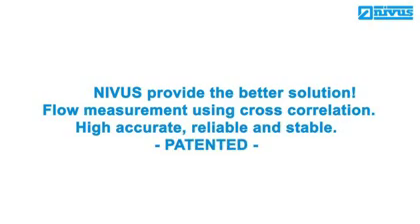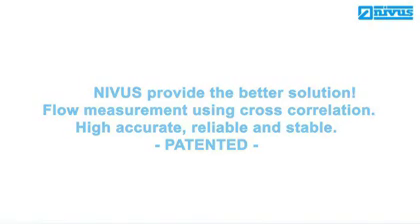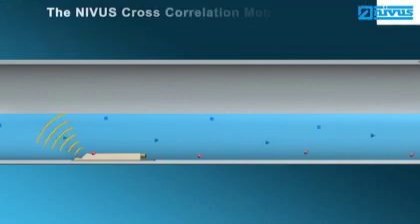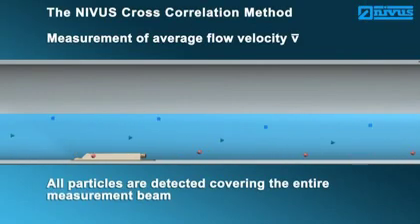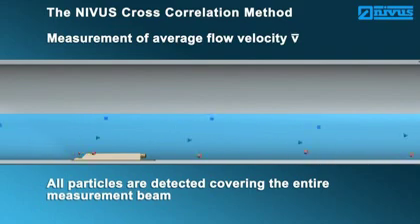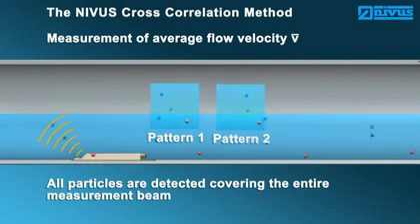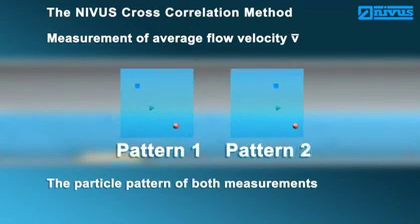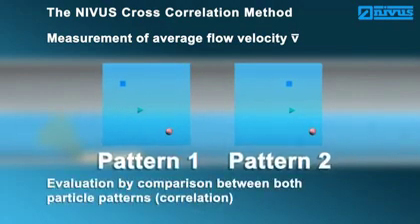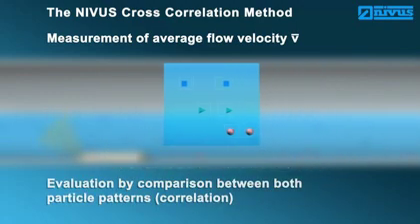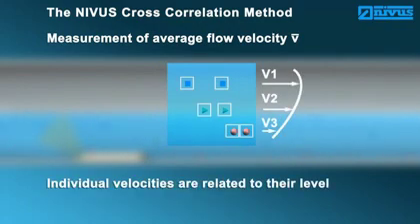NIVUS provides the better solution: flow measurement using cross-correlation — high, accurate, reliable and stable. The NIVUS cross-correlation method is not a spot velocity measurement. Here all particles are detected at the same time covering the entire measurement beam. The particle images are evaluated by comparing correlation to each other. This comparison repeats within a few milliseconds. In addition to the individual particle velocities, the relation to the flow level is available. Due to this, it is possible to represent the flow profile directly.